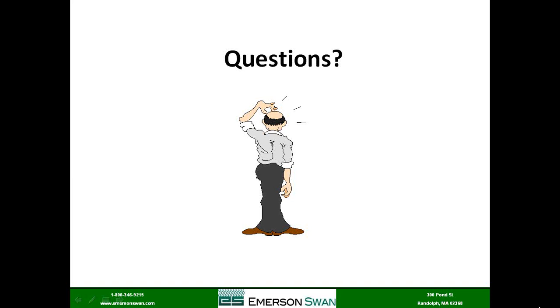Again, we don't want to rehash our previous webinar. I do encourage you, Brian, to go view that. That'll help you figure it out. But most indirects, and I learned this from Bruce because Bruce is the smartest man I know, the rated output of an indirect is based on certain assumptions of BTU boiler output, generally 145,000 to 180,000 BTU output. That's where you get the ratings on the spec sheet. If the boiler is significantly smaller than that, the ratings are going to be considerably lower, and you have to be able to reconcile the two.